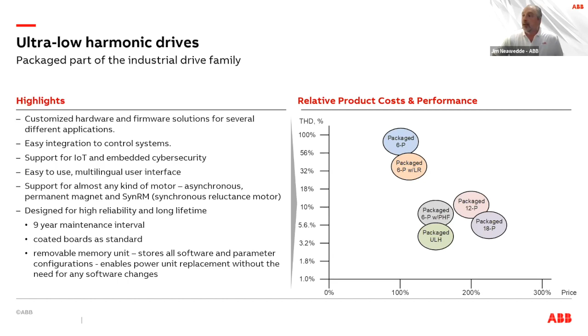So I guess the conclusion is, when it comes to harmonics, there's no need to mitigate those harmonics if you put in systems that barely create them to begin with. And there are a lot of benefits as far as avoiding penalties on your utility bill, working with generators and outside power sources like cogeneration. It also allows your motors to last longer. And it will also prevent some of those random ghosts that we see sometimes when you get harmonics. The two hardest problems I've found to diagnose in the field have been ground faults and harmonic disturbances. They're just harder to track down. So the big thing here is, you don't need to worry about mitigating those harmonics if you don't produce them initially.